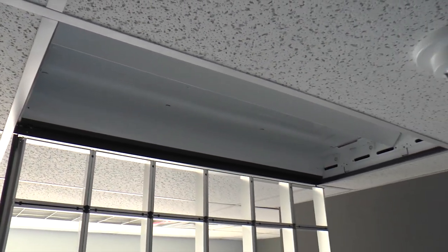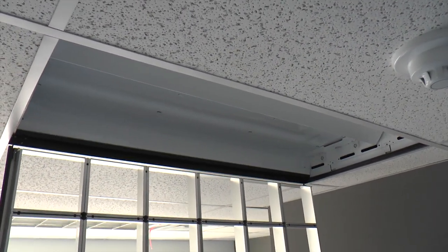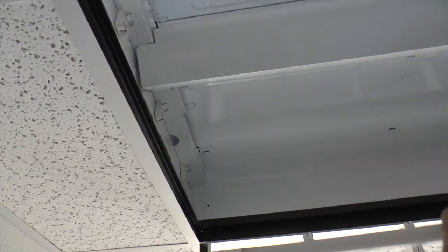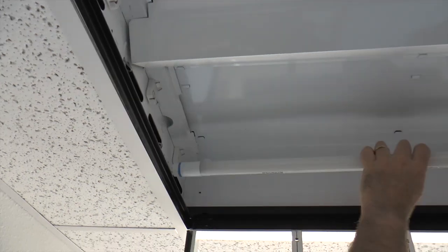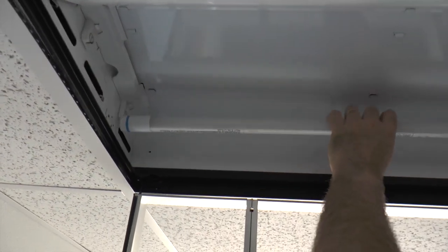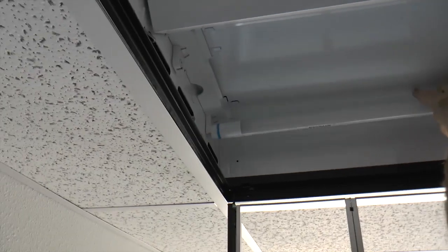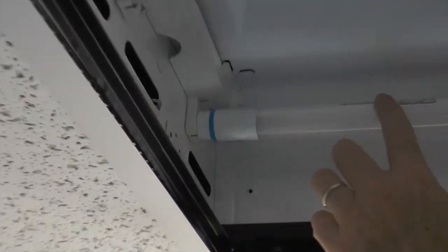And we're going to get the new plug-and-play LED T8 replacements. And we're going to install them the same way we would if the fluorescents would have burnt out. Now one of the disadvantages is when that ballast goes out, your plug-and-play is not going to work anymore. So you've got to make sure that that's always working. And you're going to have to test accordingly.